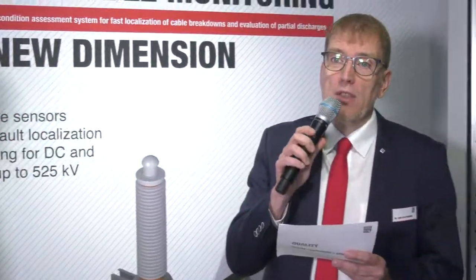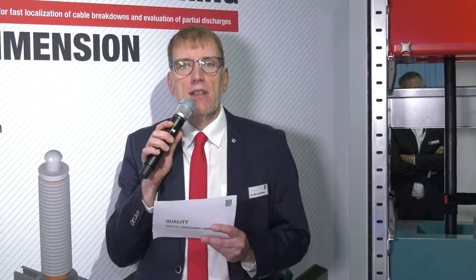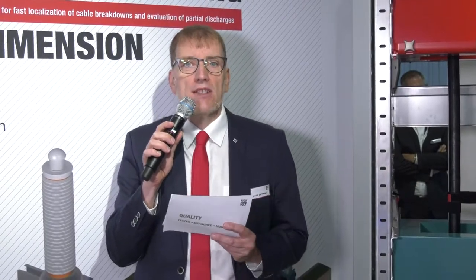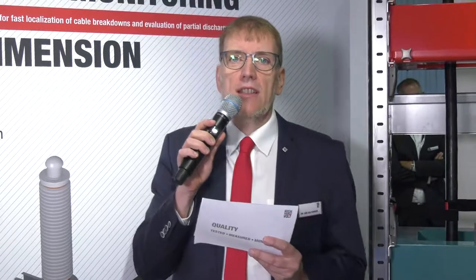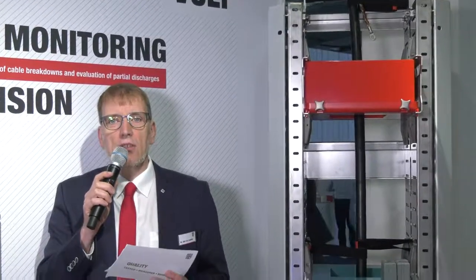Yeah, why are we doing that at all? The most important thing is that we need to guarantee also a reliable test environment to do partial discharge testing. For partial discharge testing, you have different opportunities. When we're talking about our AC, you can utilize the conventional PD measurement systems, or as we have presented also in the past, you can see here on my left, then also our non-conventional HFCTs, also suitable then for the PD measurements.